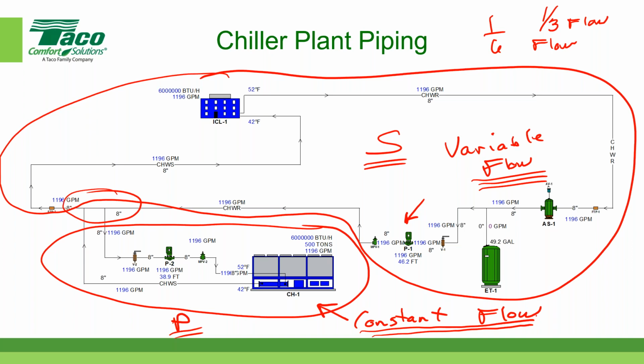All right. So what are one of the pitfalls of primary, secondary? Well, one of the pitfalls is that you have to have 2 sets of pumps, one for the primary system and one for the secondary system. And you don't get the advantage of reducing the capacity of the primary pump, because in a primary secondary system, usually the main component, the chiller or the boiler, again, is looking for constant flow.